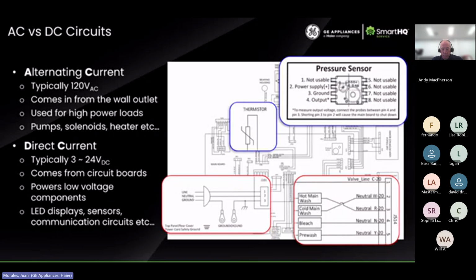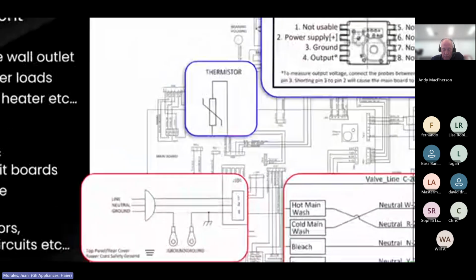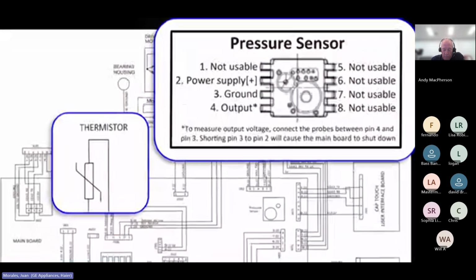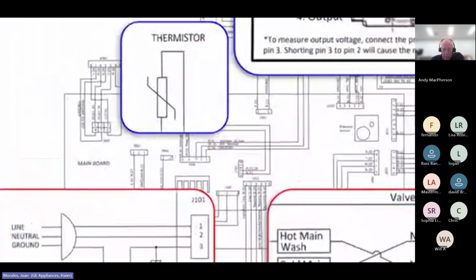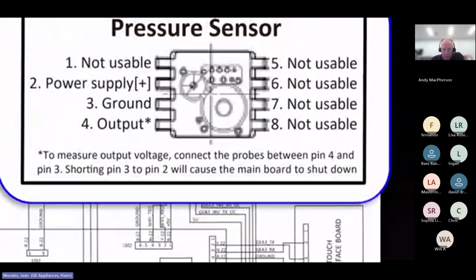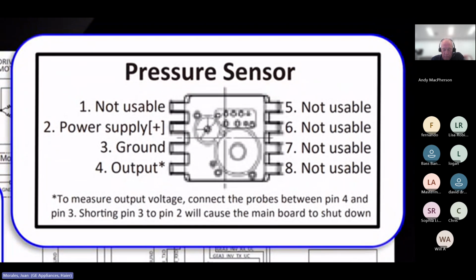Let me go ahead and zoom in over here to give you an example of why reading schematics is important for safety purposes. So if you take a look at the pressure sensor, you notice that it's got an indication at the bottom - a note that says to measure output voltage, connect your probes between pins 4 and 3, which is great. This is a great piece of information.